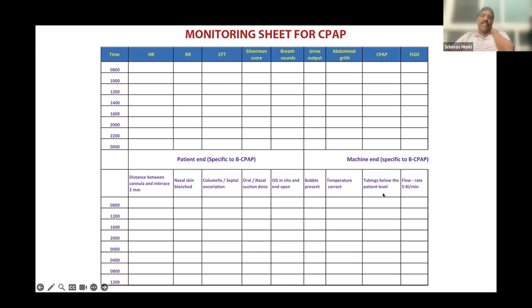And for the machine, look for the bubbles in the bubble chamber and the temperature on the humidifier. Ensure that the circuit is always kept below the level of the baby, and the flow rate should be 5 liters per minute. So this is a simple chart.